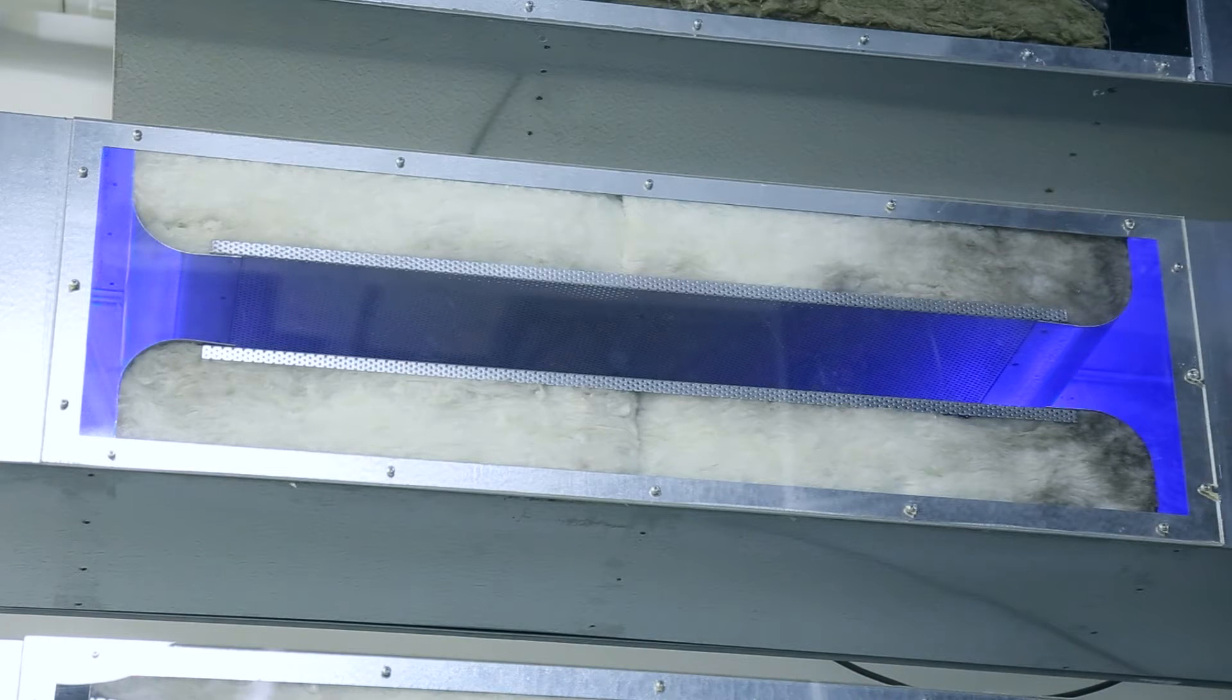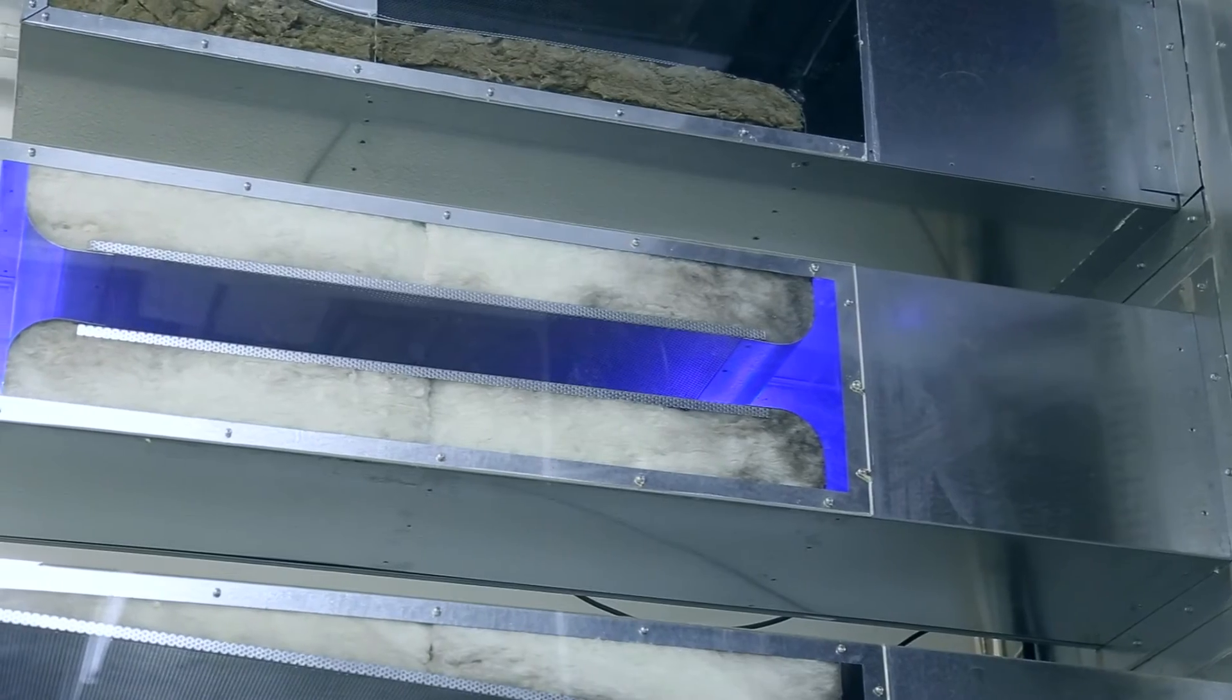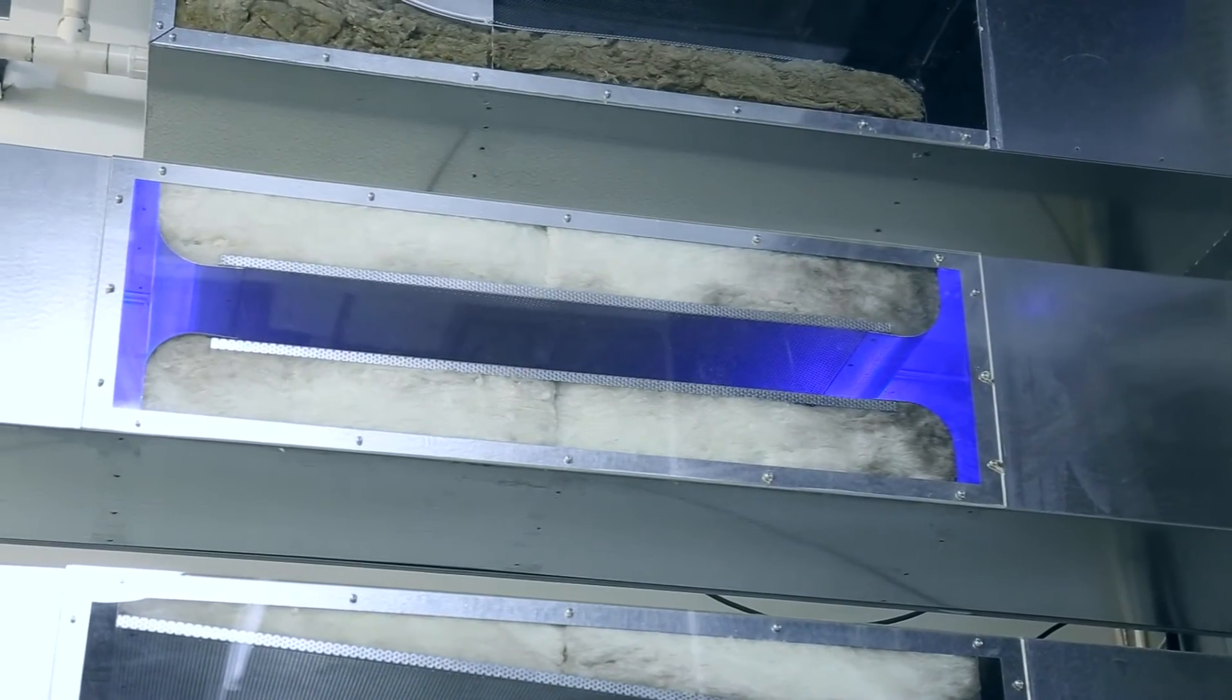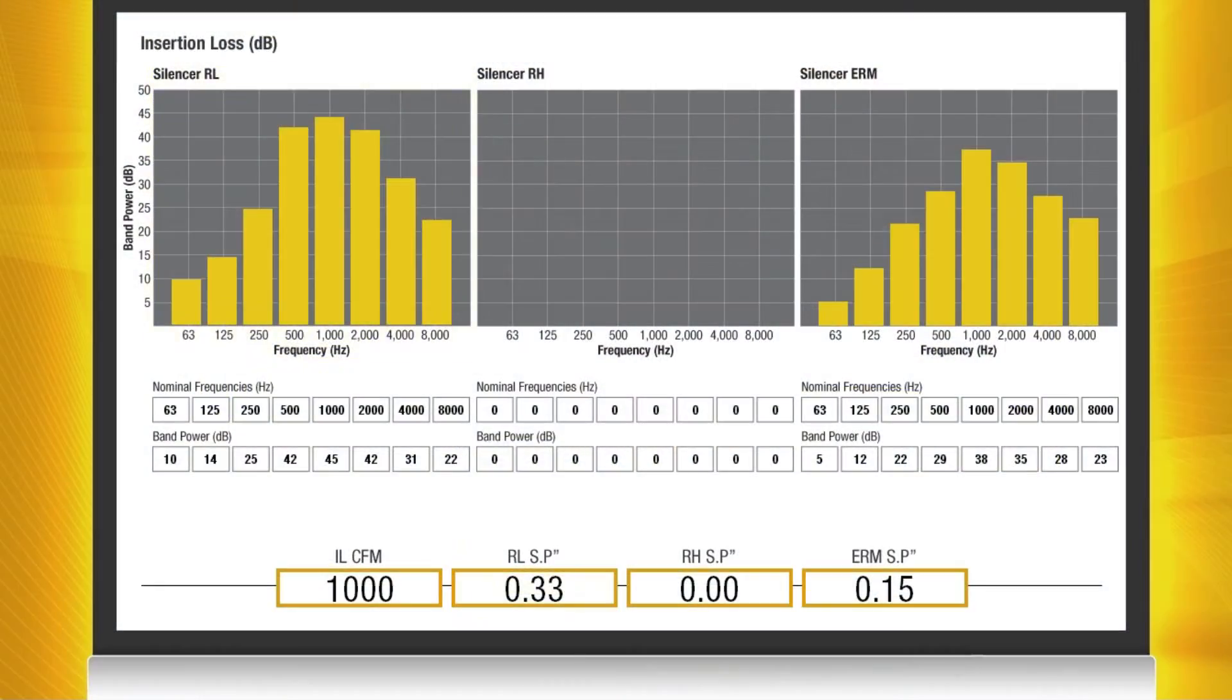As you can see the baffle configuration for the silencer is two parallel baffles with a standard fiberglass acoustic media. We'll run the sound through this silencer. The static pressure through the RL silencer is being measured at 0.33 inches. The insertion loss is also high throughout all octave bands.